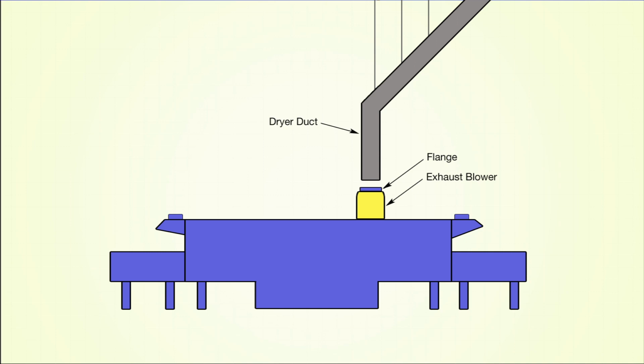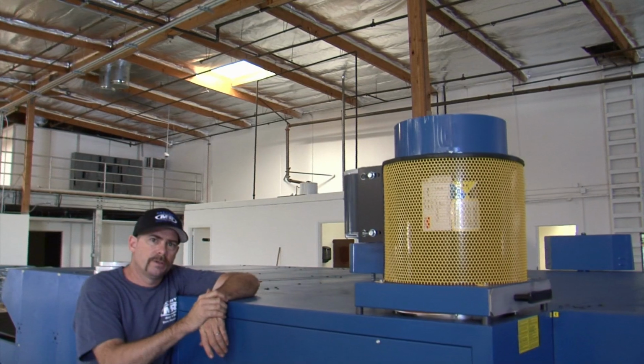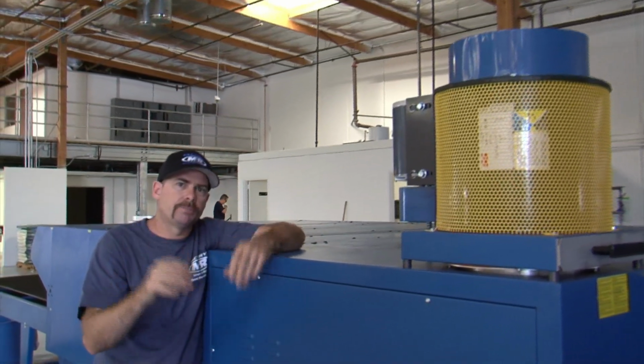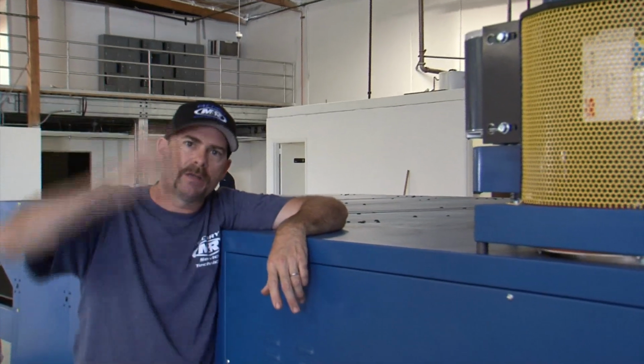exhaust blower unit. Ducting is typically done with double wall duct. Double wall creates an insulation barrier to keep the vapors hot on their way out of the building. Single wall is not permitted in most cities, so always check your local codes. It's the plumber's responsibility to work with you to ensure the ducting is done correctly.